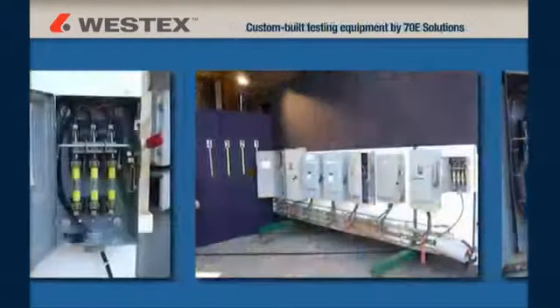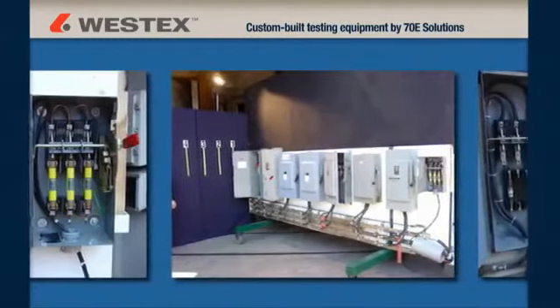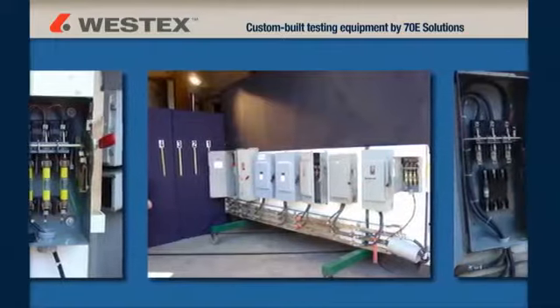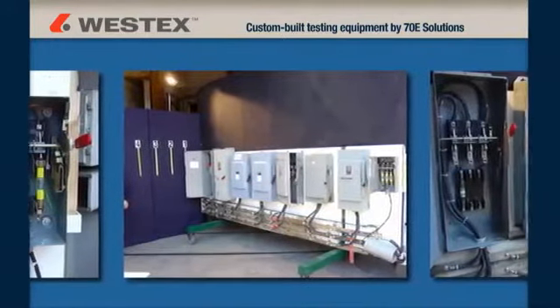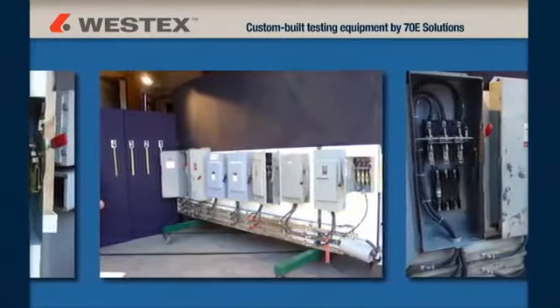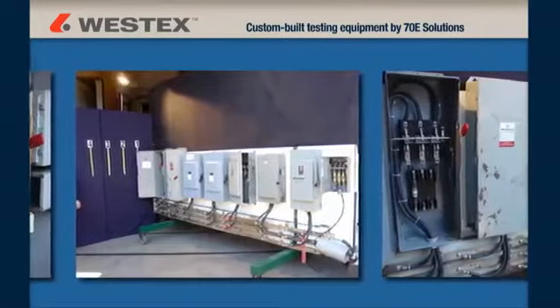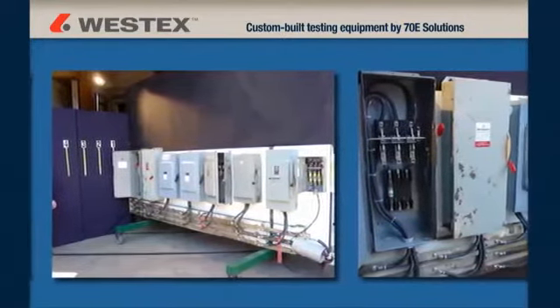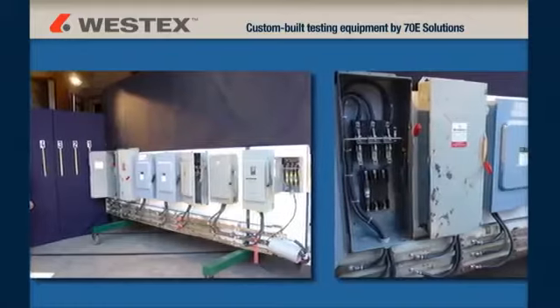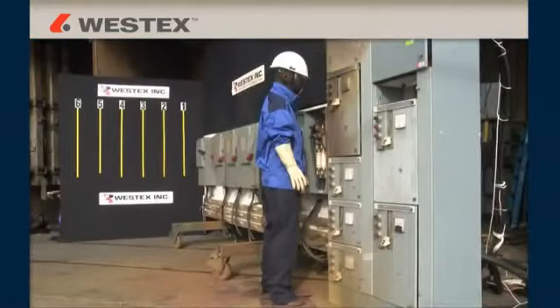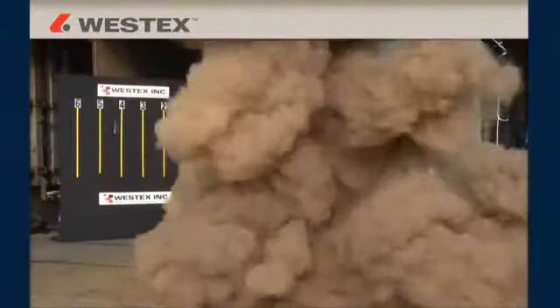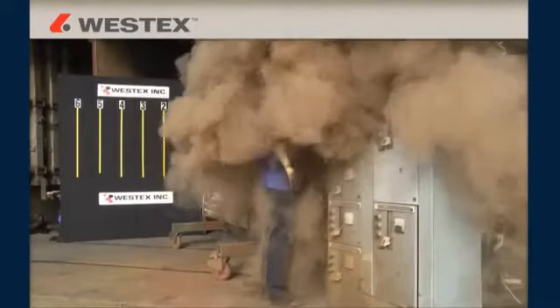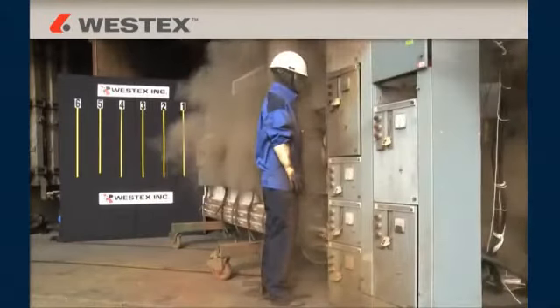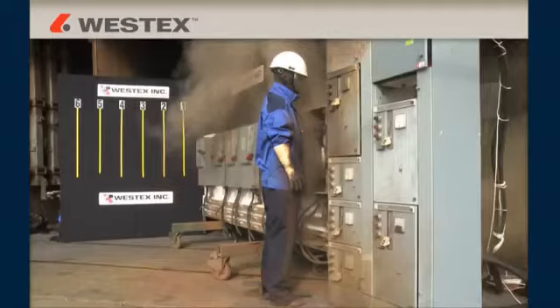Westex worked with Mike Wright of 70E Solutions to custom build a one-of-a-kind sled with a common 480-volt bus at the bottom and 30, 100, and 200 amp disconnects installed above. We created the arc flashes by placing a tool or a wire across all three phases. Our goal was to create real-world arc flashes using common 480-volt electrical equipment to help companies better understand the magnitude of the arc flash hazard that exists in nearly every facility in the world.